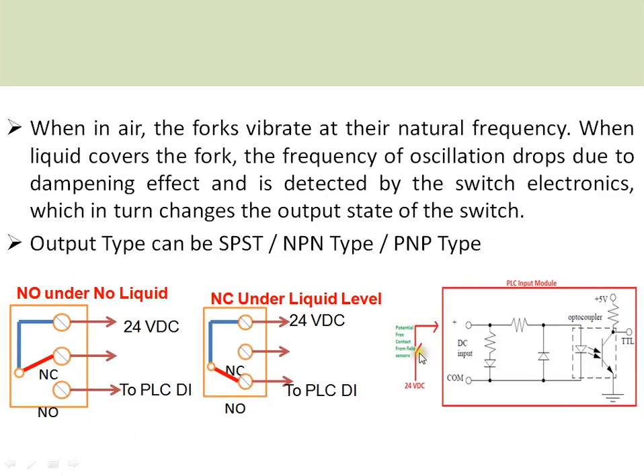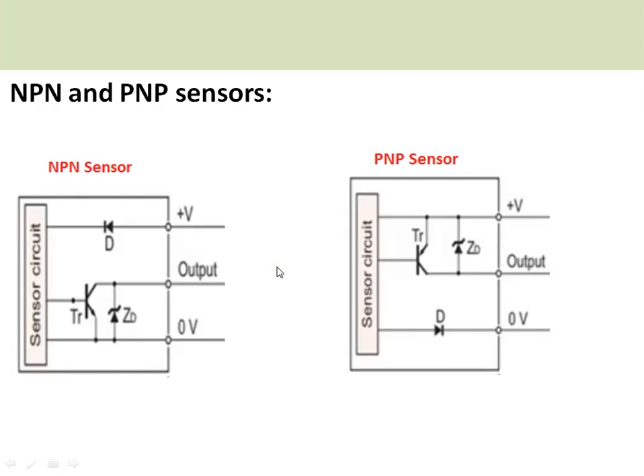The sensor can have different outputs. One is a single pole single throw switch: when there is no liquid it is a normally open switch connected to a PLC; when the liquid level is sensed, the contact changes and gives a 24-volt signal to the PLC for action as per the program. For NPN and PNP outputs — also connectable to a PLC — the NPN transistor output is a sinking sensor, and the PNP transistor output sources the current to the PLC module.